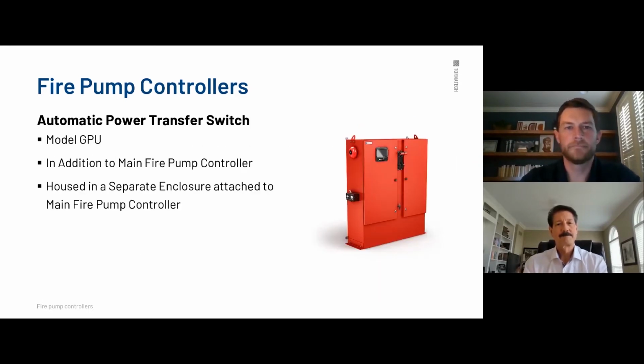Cool. All right. I'm going to start with the automatic power transfer switch. So that's what we call a GPU. So GPX is our electric line, and then plus GPU means that it has a transfer switch on it. So let me show you this little section right here. That's going to be the transfer switch. So you've got the normal side on the left side, and then the automatic transfer switch is housed over here on the right side, which is where it is housed in a separate enclosure and attached to the main fire pump controller.